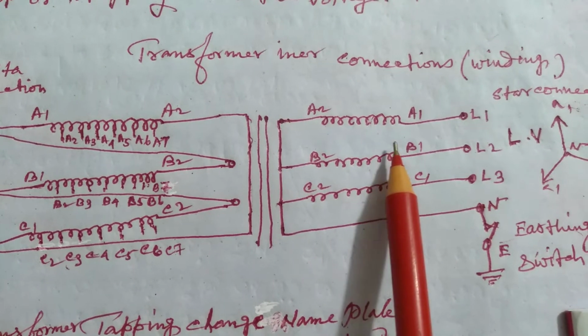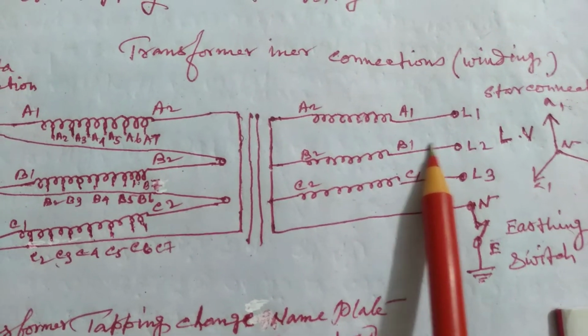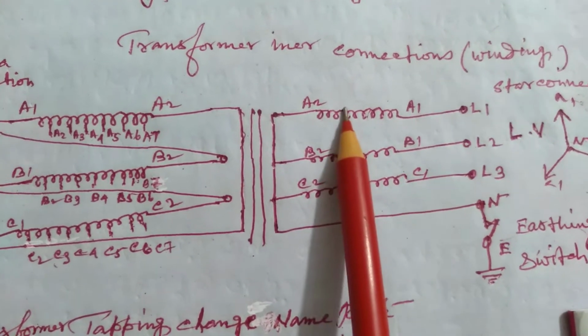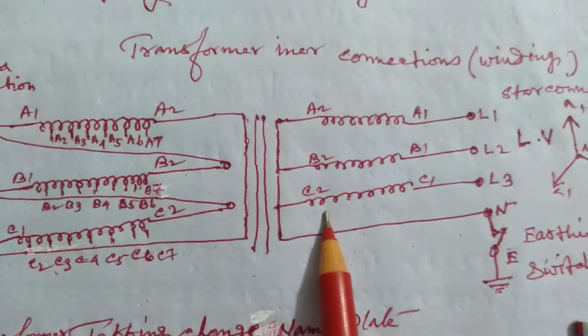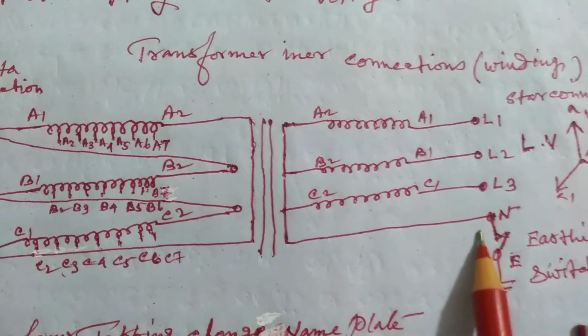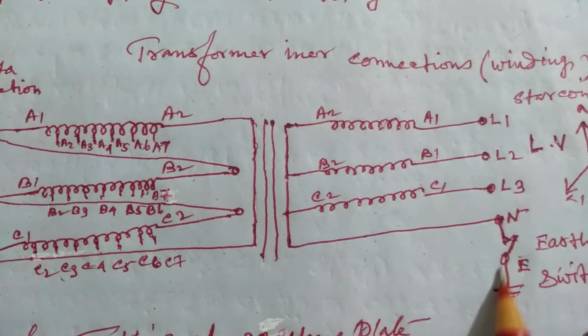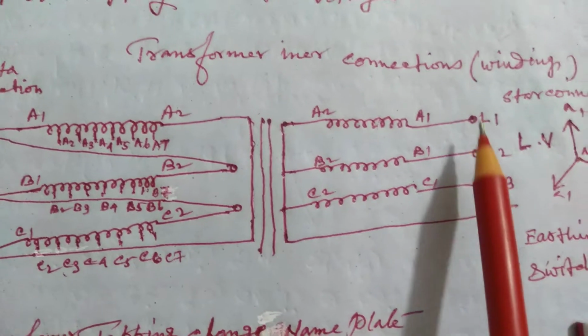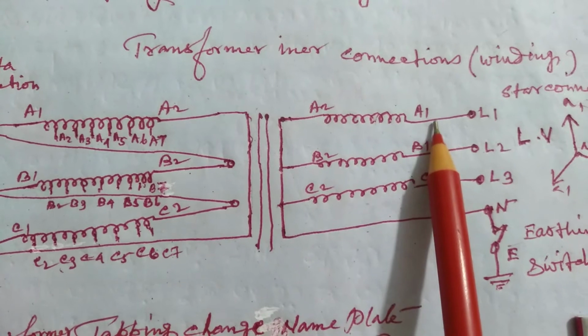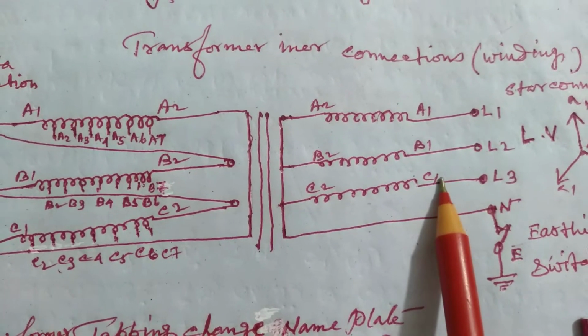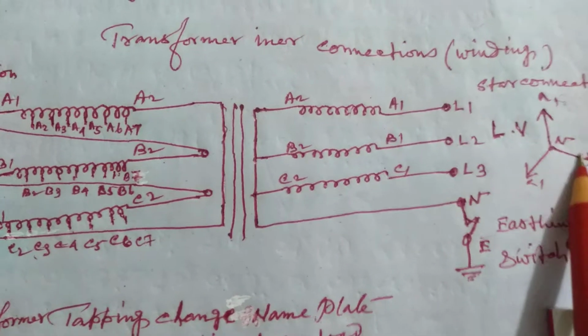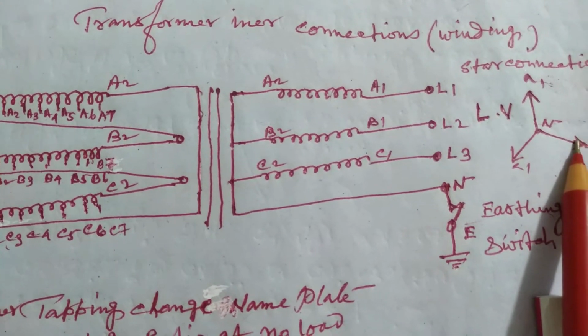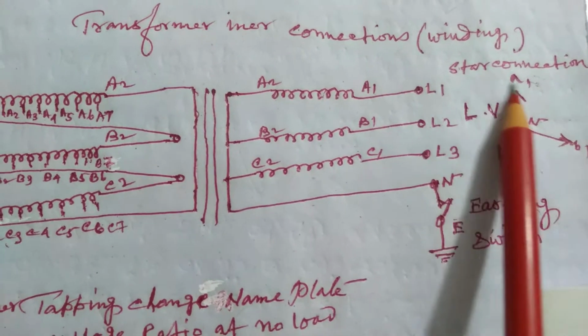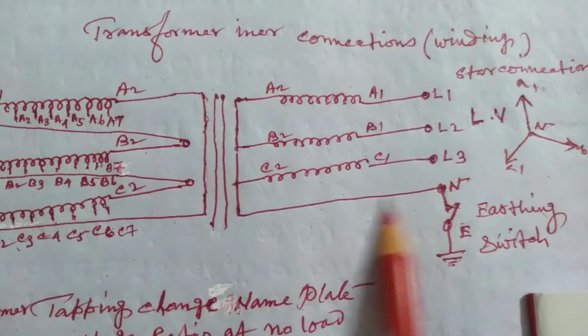step down is the secondary. A2, B2, C2 are shorted as the neutral point in the switching system to earth. Outer A1, B1 and C1. This is the LV side. This is star connected. Star connection symbol.